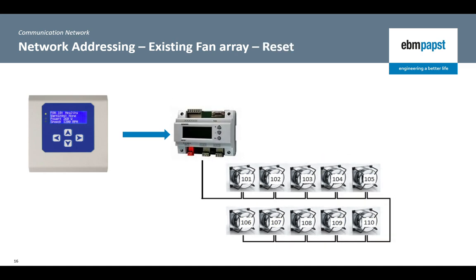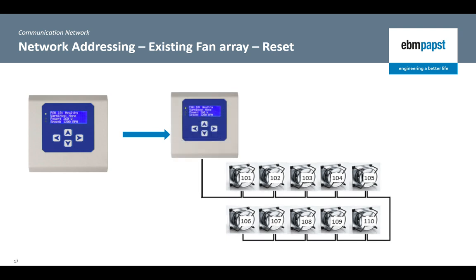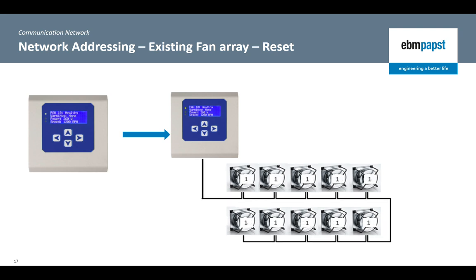If, however, the MDC controller is being used to replace a third-party application controller that has assigned specific device addresses for each fan in the array, the network of fans must be reset back to their factory default conditions and the network re-initialised as a new fan array. As described previously, the MDC will search for a fan with Modbus Device Address 2 when connecting to an existing array. In this case, if the first device in the network has been assigned address 101, the MDC starts by searching for Modbus Device Address 2, it will not move on until it has been found and the network initialisation will be unsuccessful. By resetting the fans back to default address 1 for every fan in the array, the MDC can connect to the fans as if it was a brand new installation.